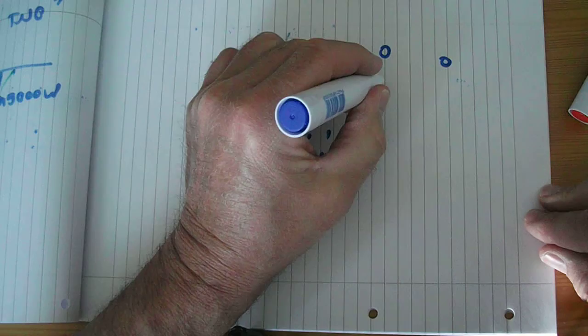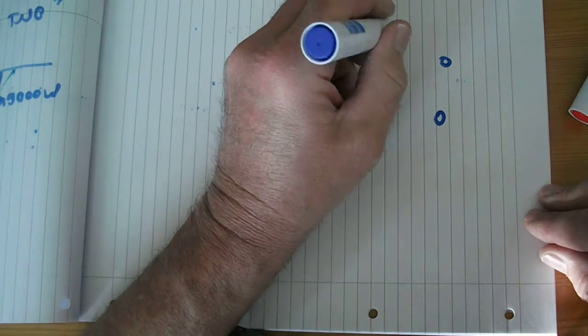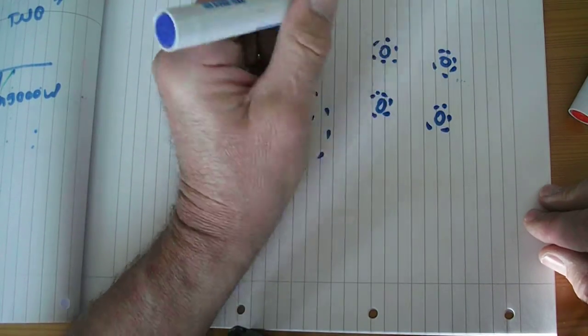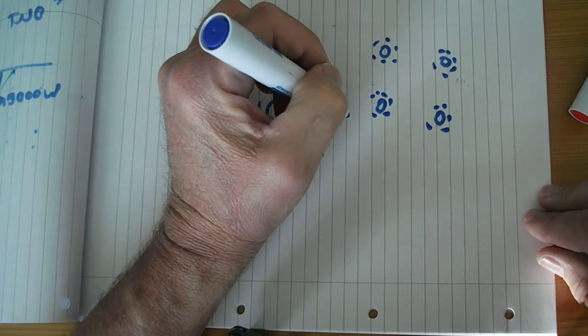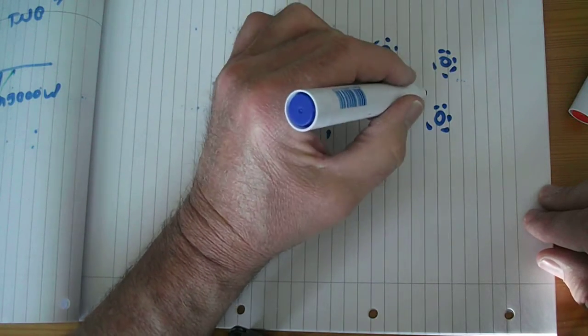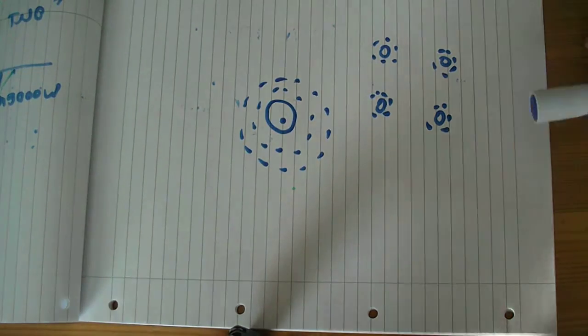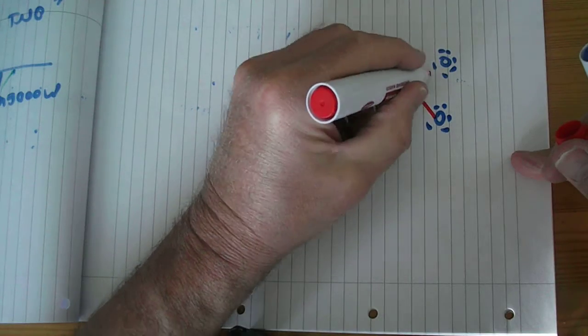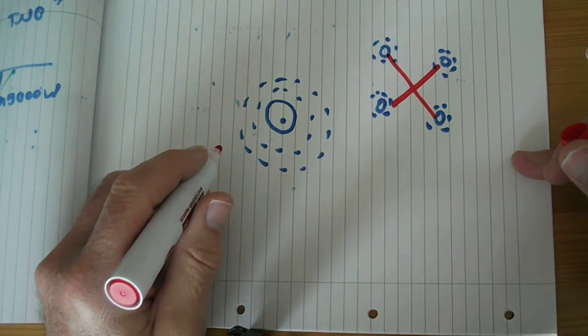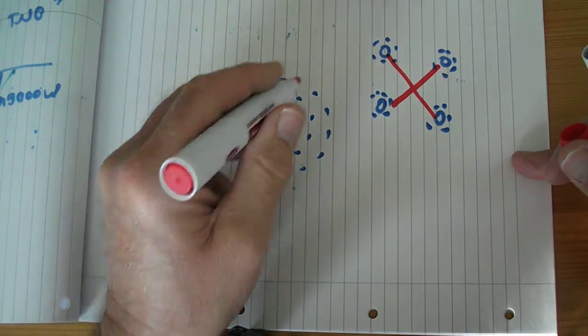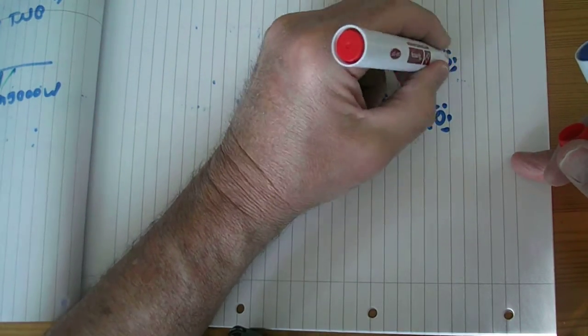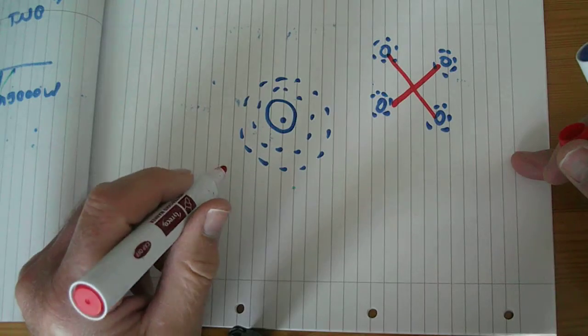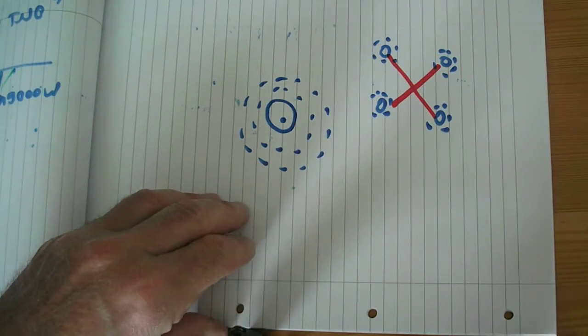So a way of reducing this effect is to split this single conductor into, say, 2 or 4 single conductors, and so because the current is divided by 4 into each conductor, the field is reduced. So the overall effect of the field is reduced. And if you use a spacer to keep these apart, then the effect works quite well, because the current is effectively divided into 4, so you've got 4 smaller fields, so the overall effect is less. So that's why you have these spacers. Okay.